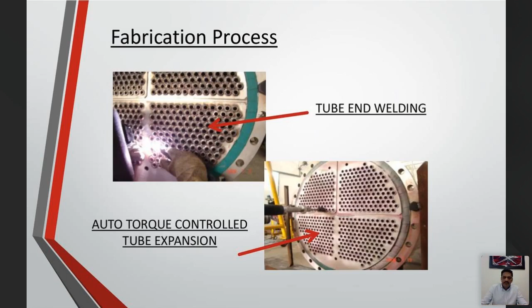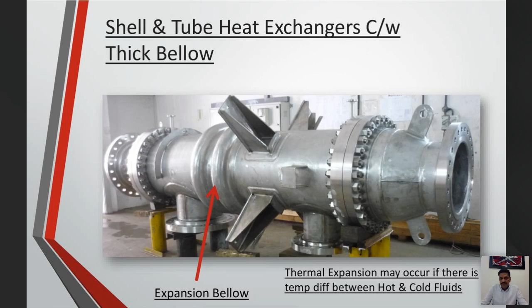Here are some other photos of heat exchangers with bellows. It's called expansion bellow. Why do we need an expansion bellow? Because if the temperature difference between cold fluid and hot fluid is too huge, then there will be thermal expansion in the shell body. So you have to put an expansion bellow. It is not necessary that all heat exchangers should have this bellow. It only depends on the application and the temperature difference.